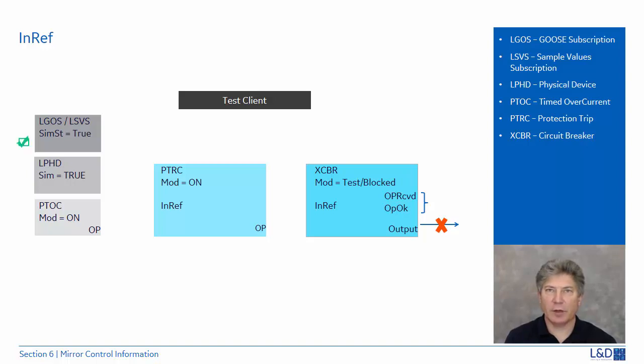So to begin, the LSVS, or the logical node sampled values, is set to simulation mode. The LPHD logical node is set to simulation mode. The phase time overcurrent logical node is enabled for operation. The protection trip logical node is enabled for operation. The XCBR circuit breaker logical node is set to test blocked to prevent the output from operating.